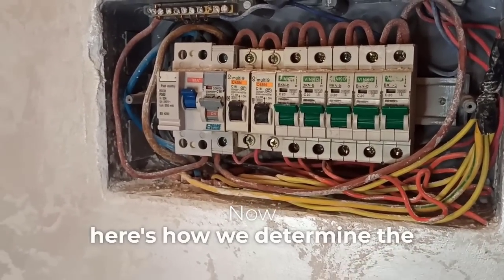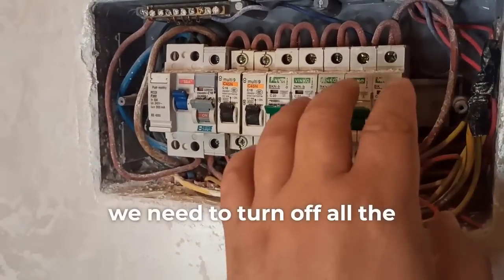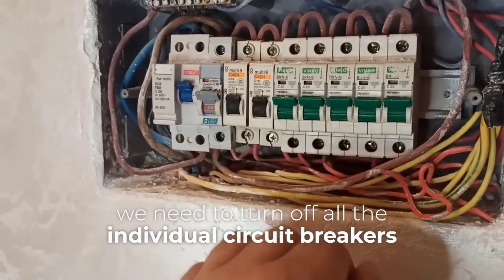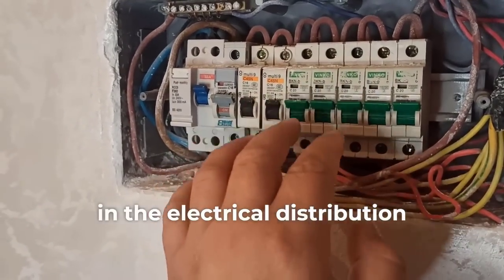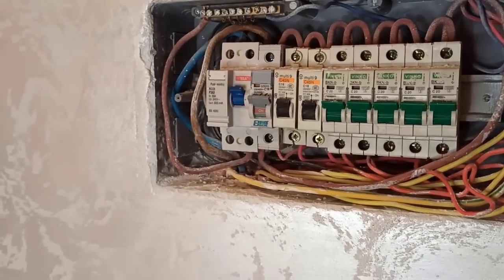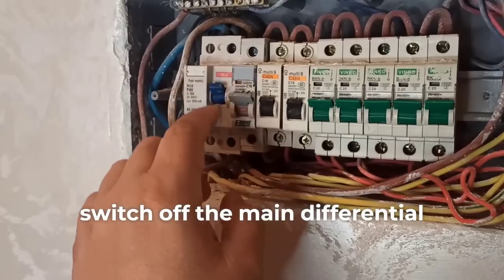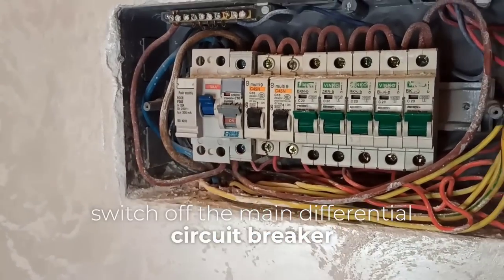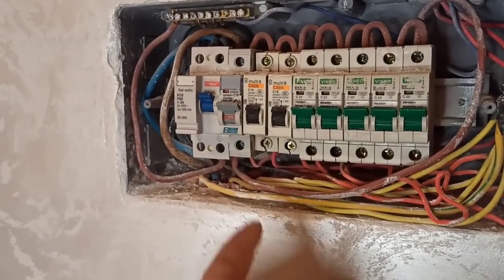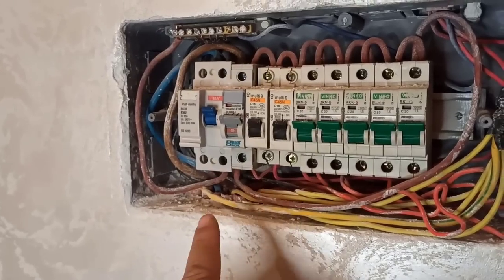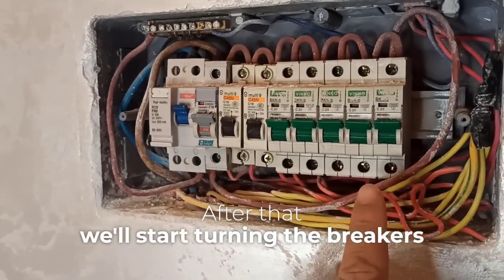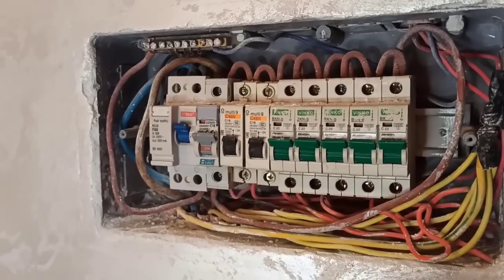Now, here's how we determine the issue. First, we need to turn off all the individual circuit breakers in the electrical distribution panel. Then we'll switch off the main differential circuit breaker. After that, we'll start turning the breakers back on one by one.